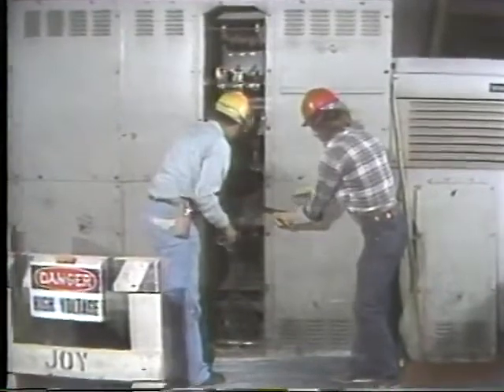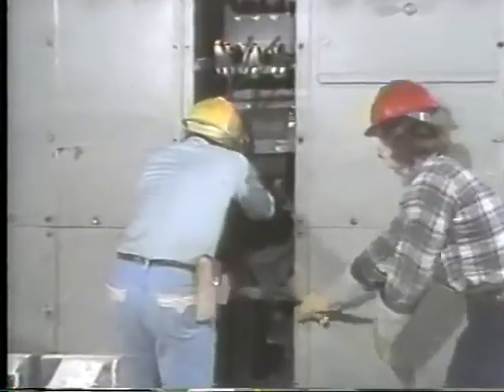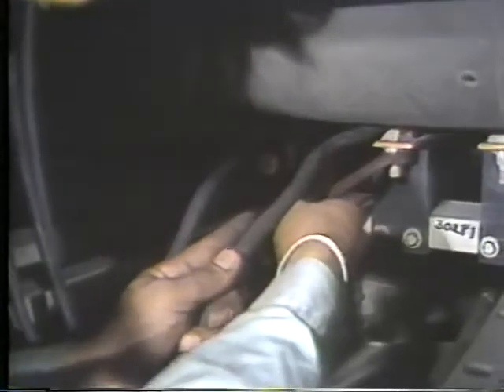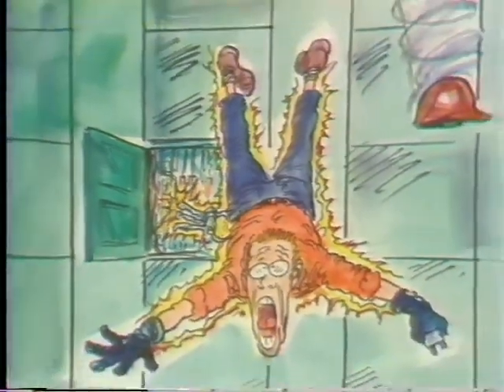In this case, it was safer to insulate the surrounding bus bars and then work without gloves. In this tight space, gloves would make the operation much clumsier. So as long as everything is de-energized or insulated with blankets, working barehanded is safer and faster. You'll notice, though, that nobody's wearing keys on their belt or has metal jewelry on. You shouldn't either, unless you're itching to play human lightning rod.